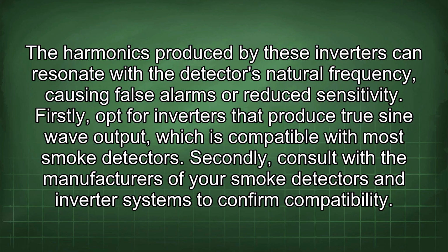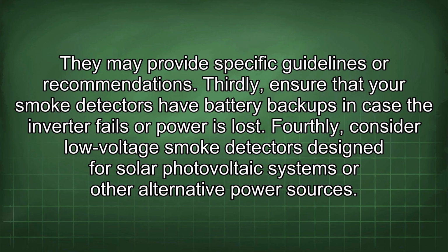Firstly, opt for inverters that produce true sine wave output, which is compatible with most smoke detectors. Secondly, consult with the manufacturers of your smoke detectors and inverter systems to confirm compatibility. They may provide specific guidelines or recommendations. Thirdly, ensure that your smoke detectors have battery backups in case the inverter fails or power is lost. Fourthly, consider low-voltage smoke detectors designed for solar photovoltaic systems or other alternative power sources.